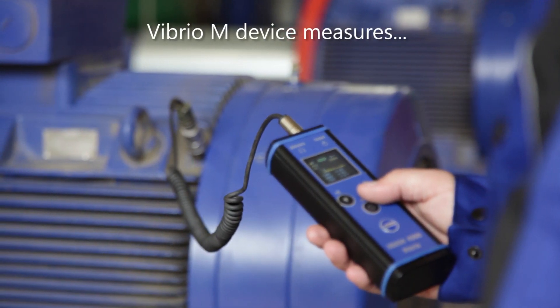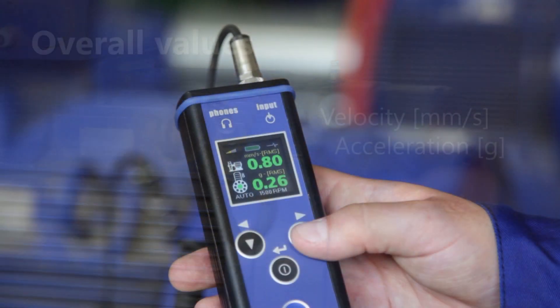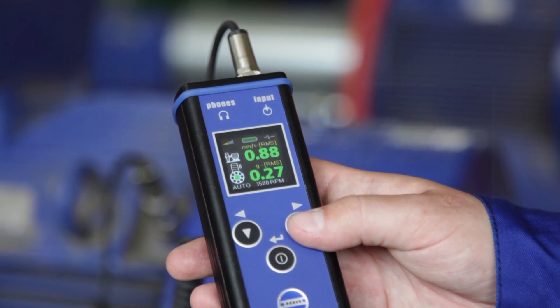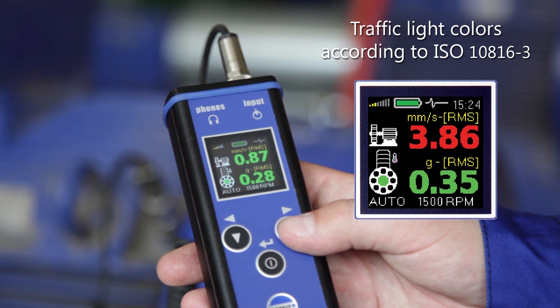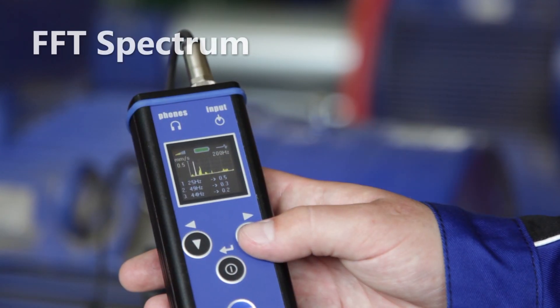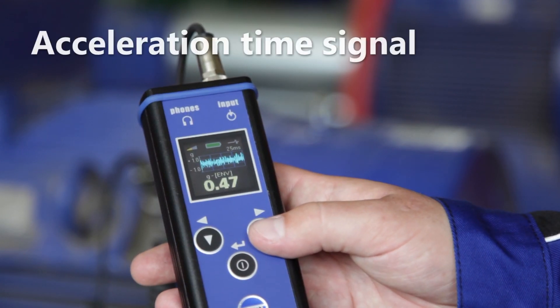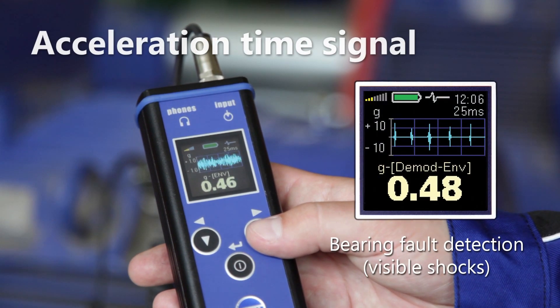The Vibrio M device measures overall values, velocity and acceleration, for which evaluation ISO 10816 is used. You can also measure FFT spectrum and the demodulated acceleration time signal for bearing fault detection.